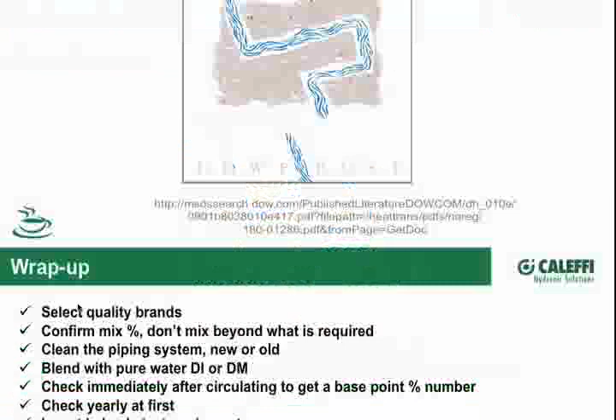I would caution people, don't try to use automotive or RV antifreeze in your system. I know it's tempting because of the cost, but they don't have anything in there that's right for what we do. Well, automotive antifreeze is exactly that, designed for protecting automotive cooling water systems, so they have additives specific to aluminum at high temperature, and those additives won't have a long lifetime. A long-life automotive antifreeze is about 5 years, so you want to replace it every 5 years, following the manufacturer's recommendation. That's the reason you wouldn't put it in an HVAC system, since you don't want to replace that fluid every 5 years, you want it to run hopefully 20 years.